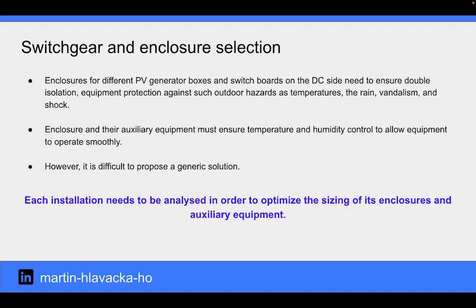Switchgears and enclosure selection. Enclosures for different PV generator boxes and switchboards on the DC side need to ensure double isolation, equipment protection against such outdoor hazards as temperatures, the rain, vandalism, and shock. Enclosures and their auxiliary equipment must ensure temperature and humidity control to allow equipment to operate smoothly. It is, however, difficult to propose a generic solution. Each installation needs to be analyzed to optimize the sizing of its enclosures and auxiliary equipment.